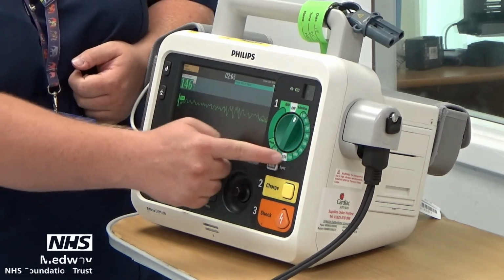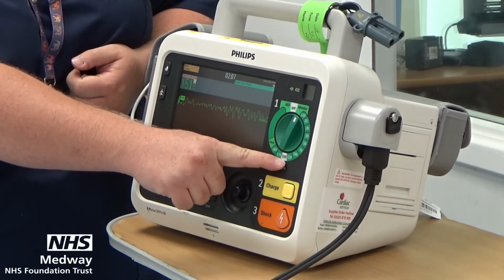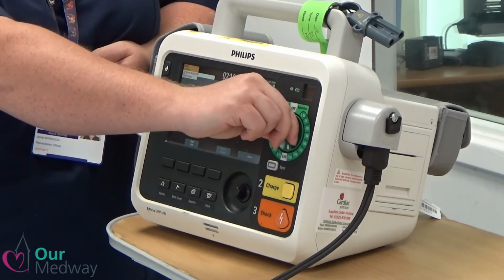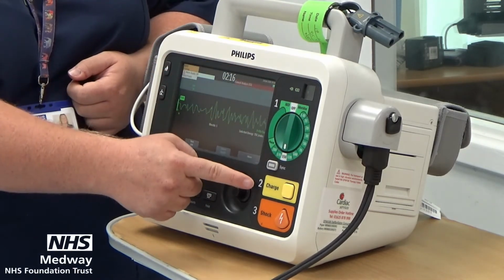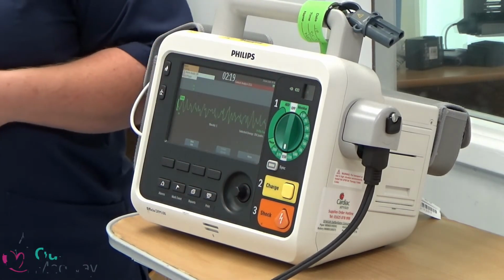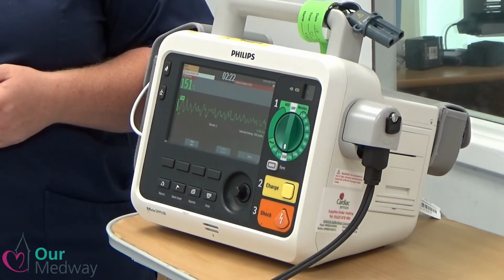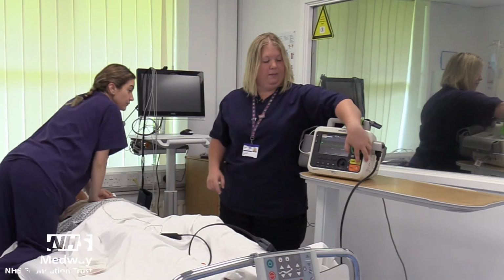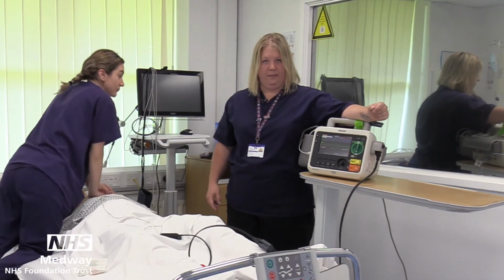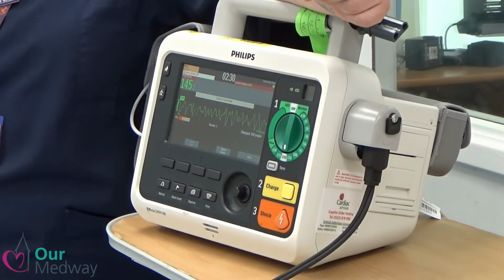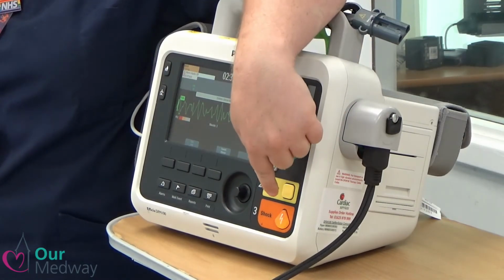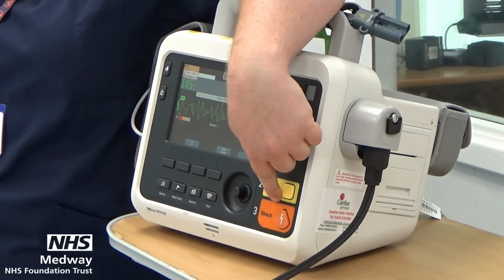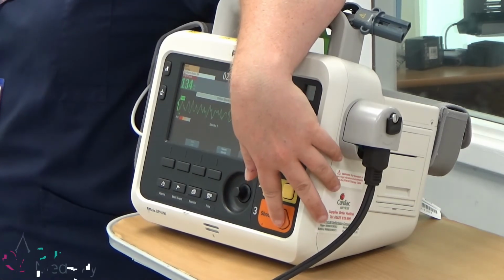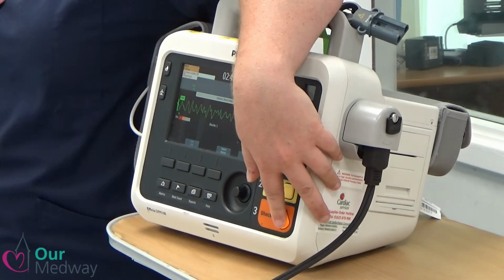On the dial here, you'll see that 150 is a different colour. That's because every shock we deliver is delivered at 150 joules, non-escalating. So I dial to 150 and then I charge. The difference here is that Andrea can continue chest compressions whilst I charge the device. When it's ready for shocking, there'll be a change in pitch and the shock button will flash. At this point, everybody must be clear of the bed. So everyone clear, please. Oxygen away. I'm shocking. Shock delivered. Please return to chest compressions.